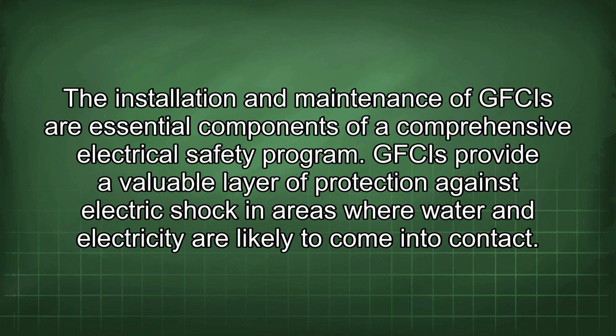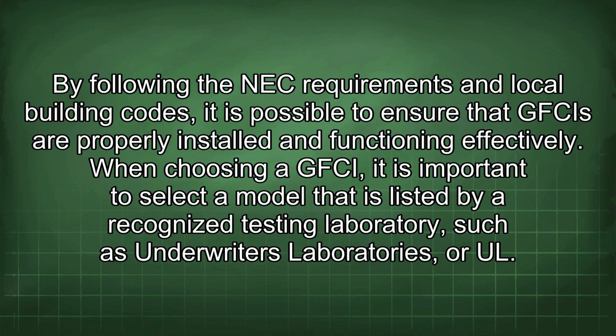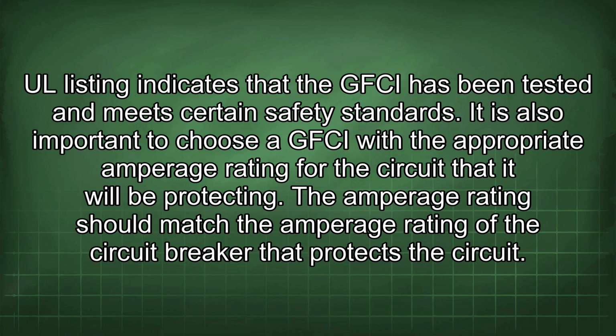The installation and maintenance of GFCIs are essential components of a comprehensive electrical safety program. GFCIs provide a valuable layer of protection against electric shock in areas where water and electricity are likely to come into contact. By following the NEC requirements and local building codes, it is possible to ensure that GFCIs are properly installed and functioning effectively. When choosing a GFCI, it is important to select a model that is listed by a recognized testing laboratory, such as Underwriters Laboratories or UL. UL listing indicates that the GFCI has been tested and meets certain safety standards. It is also important to choose a GFCI with the appropriate amperage rating for the circuit that it will be protecting. The amperage rating should match the amperage rating of the circuit breaker that protects the circuit.